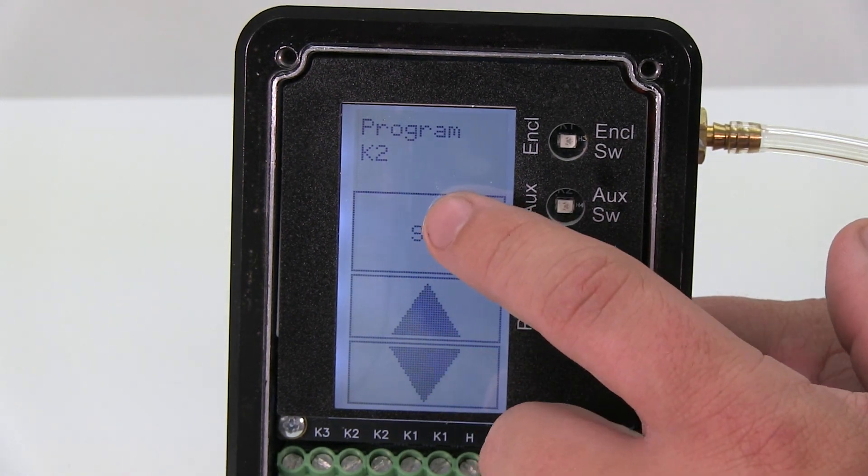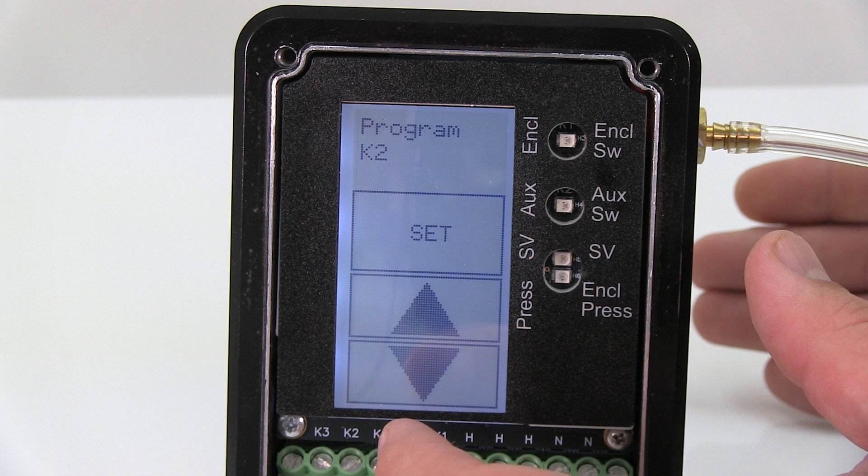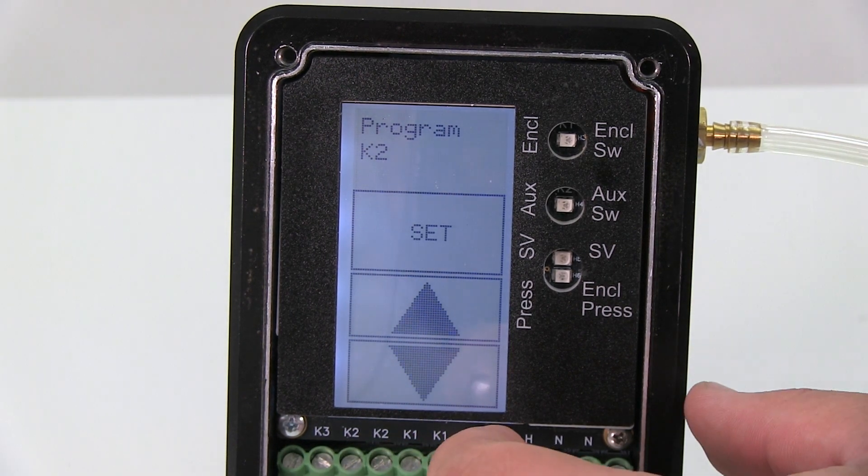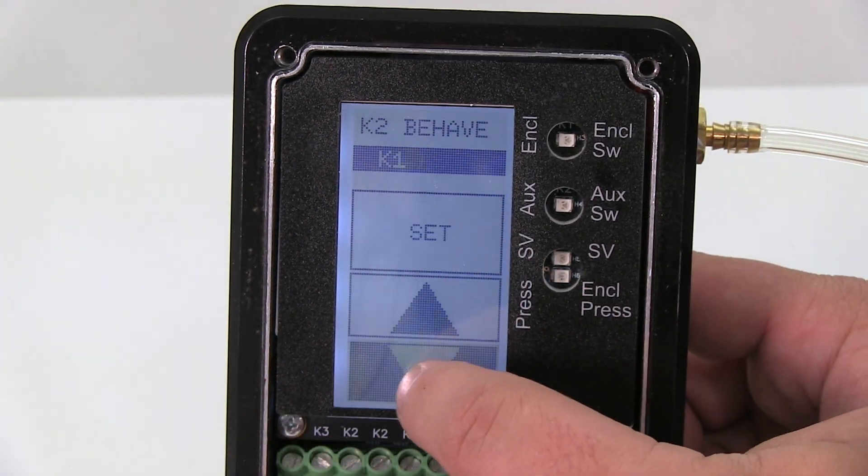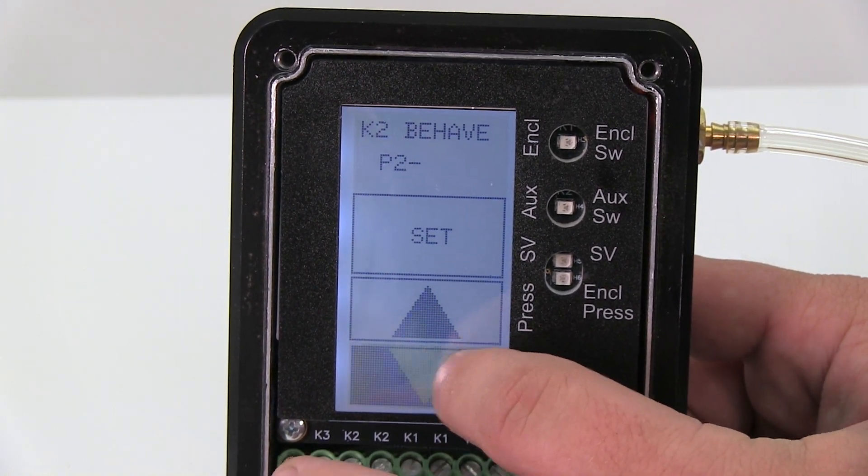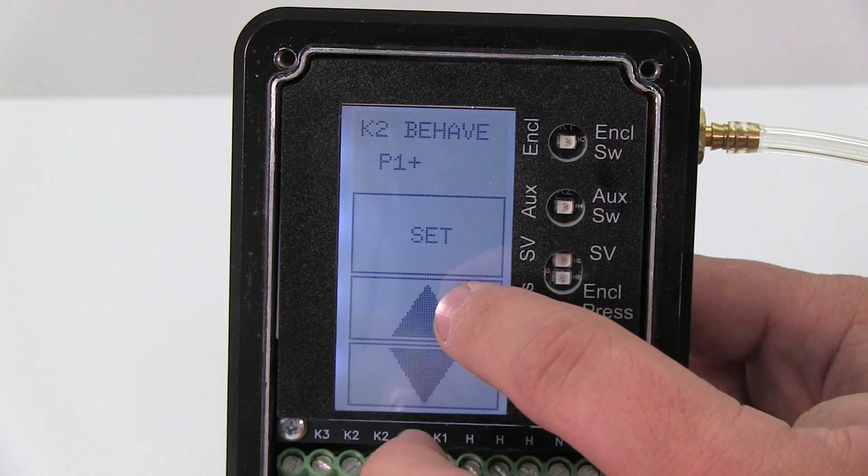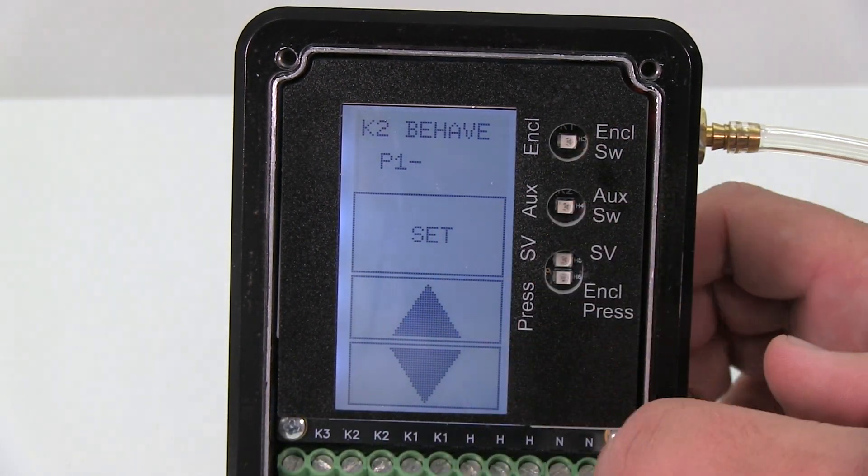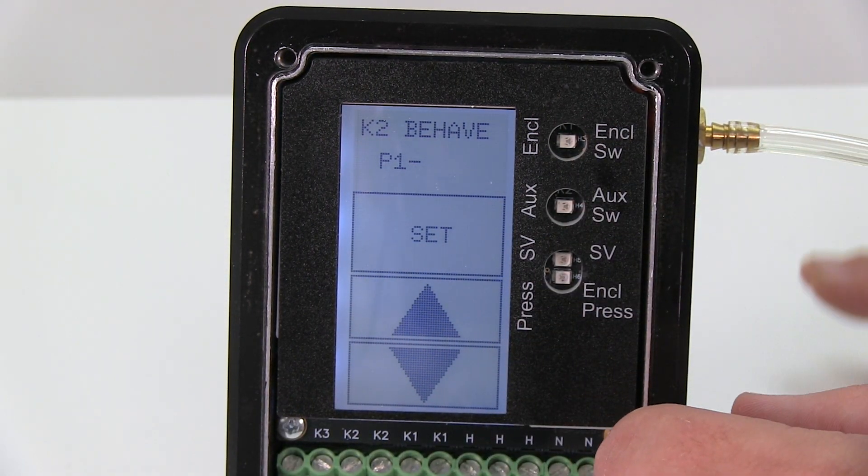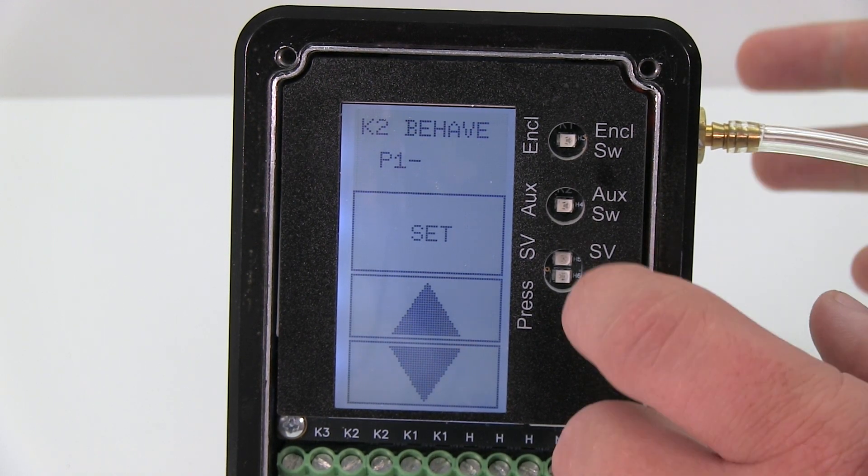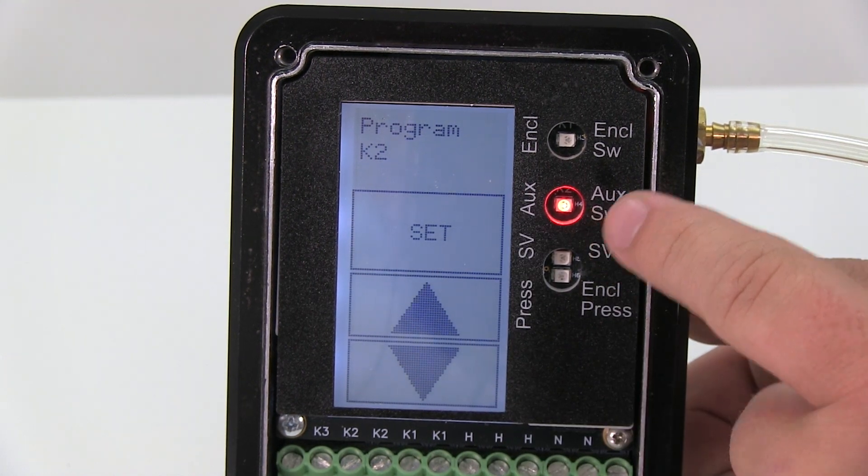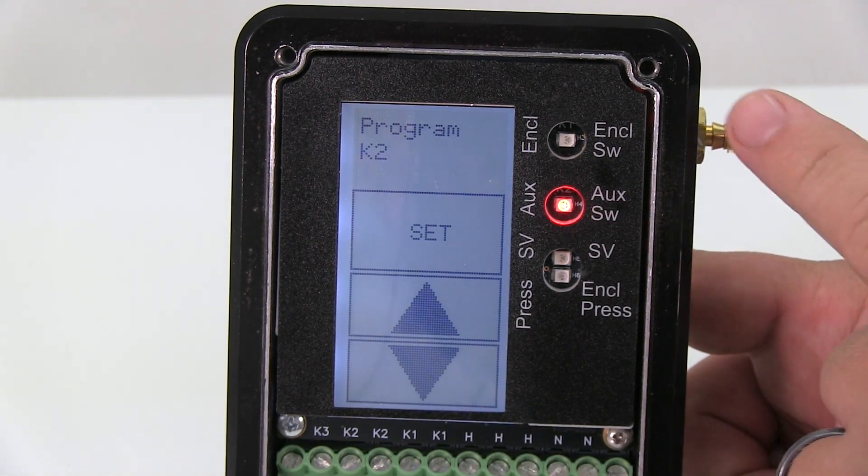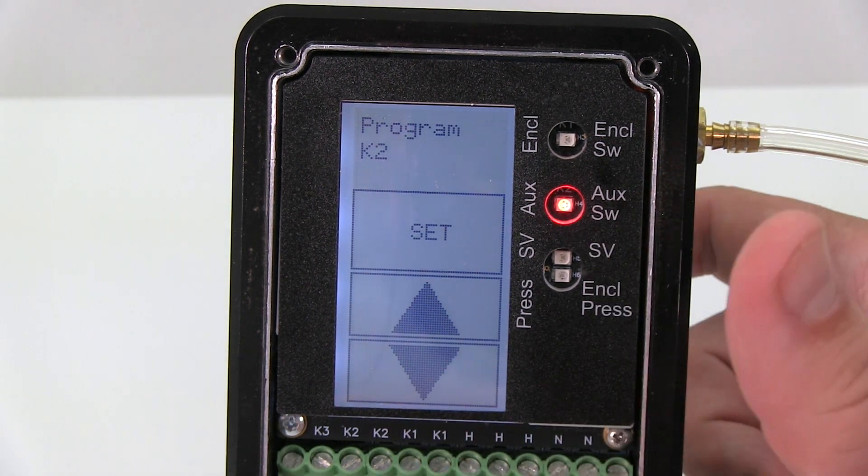If I hit set, my next function K2 - that's my alarm contact. Typically if you lose positive pressure in the enclosure and you want to set off an alarm, you would program K2 to P1 minus. So your minimum pressure set point - if P1 minus means if my pressure drops below my minimum pressure set point or my safe pressure, the K2 contact will energize, setting off an alarm in my enclosure. As you can see there, because I have no reference pressure going to this unit, my K2 contact kicked on, telling me that I have an alarm.